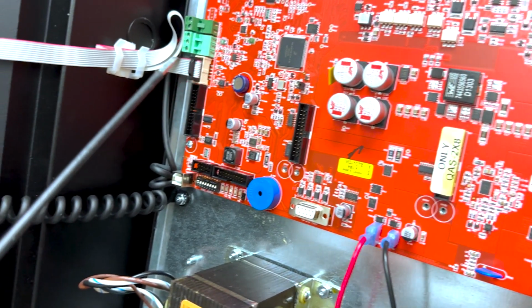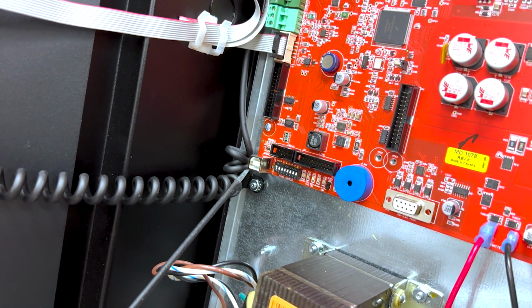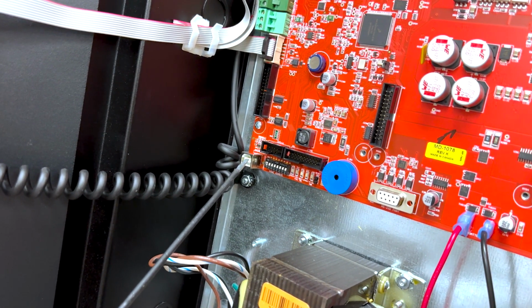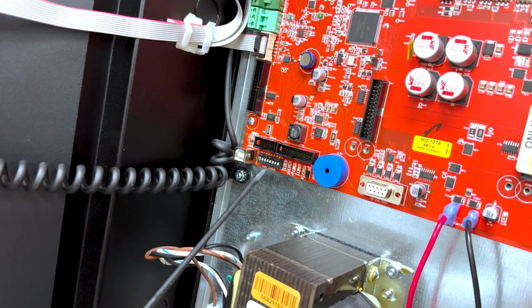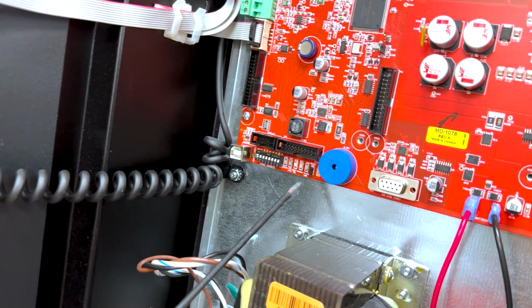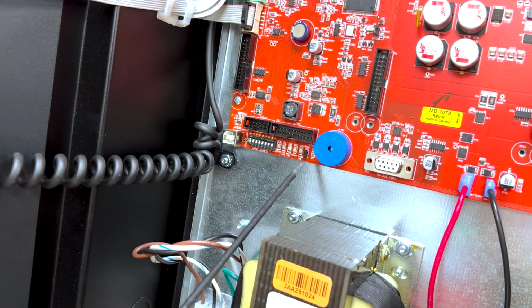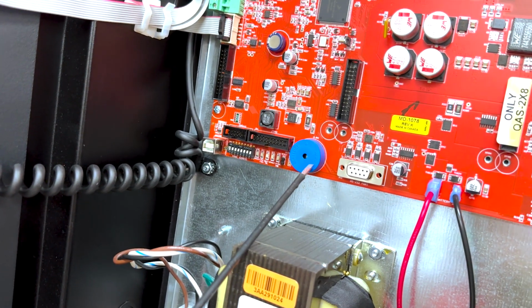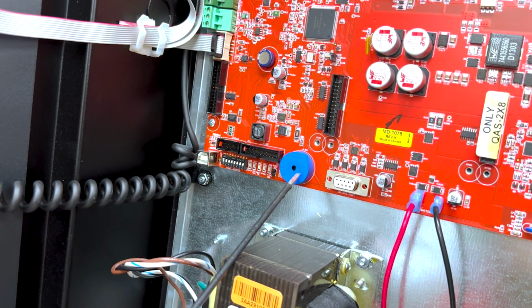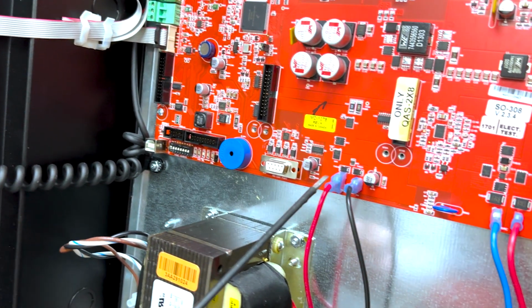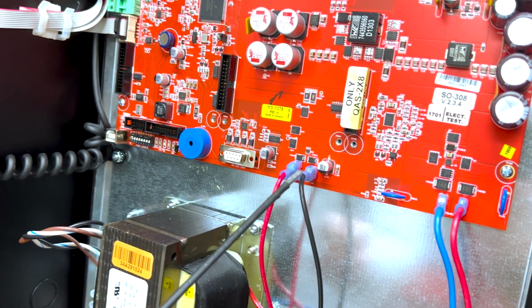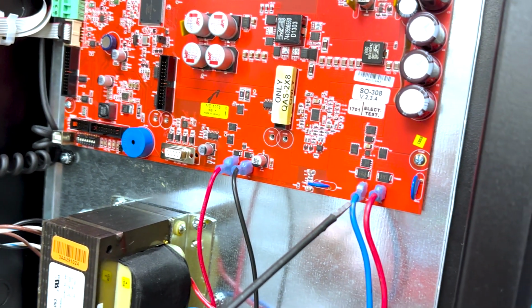At the bottom left-hand corner, we have the USB Type-B port for programming the panel, and next to that, we have the RS485 address dip switch bank for addressing the panels. To the right, we have the reset jumper. When momentarily shorted, it will reset the panel. In blue, we have the panel's trouble buzzer. To the right, we have the positive and negative battery terminals. And finally, the 29-volt AC transformer input.